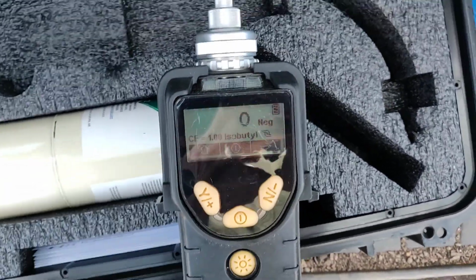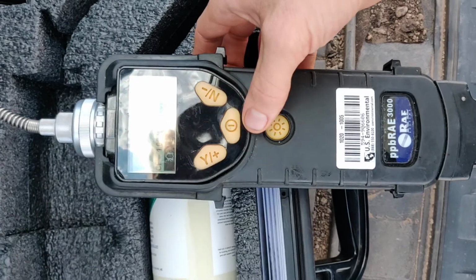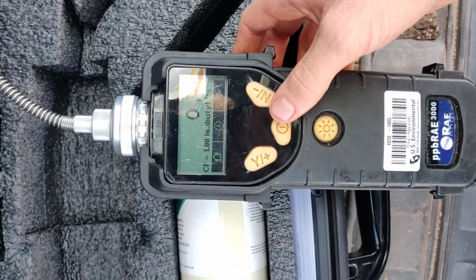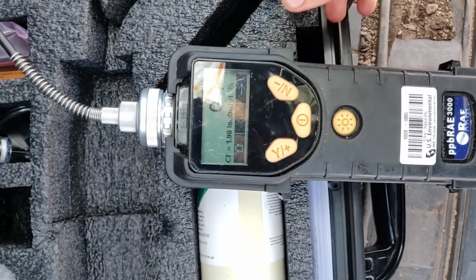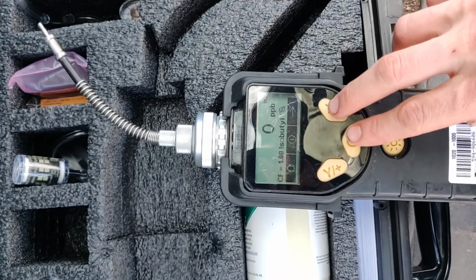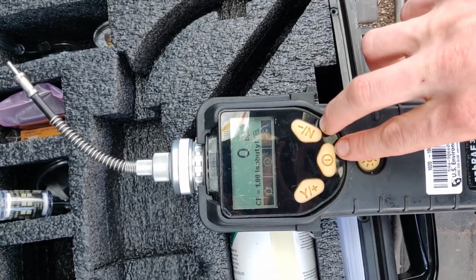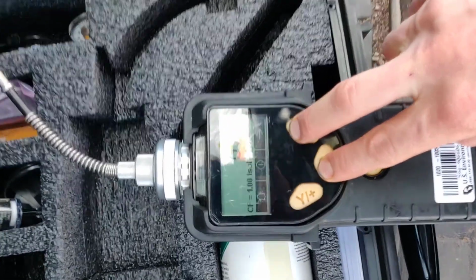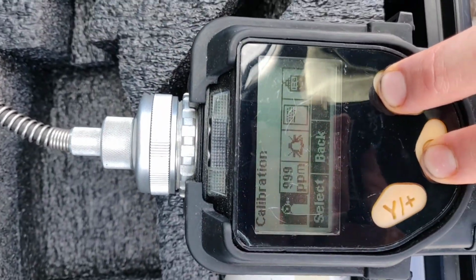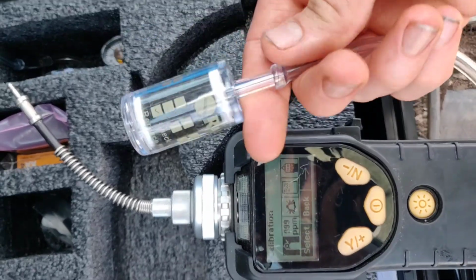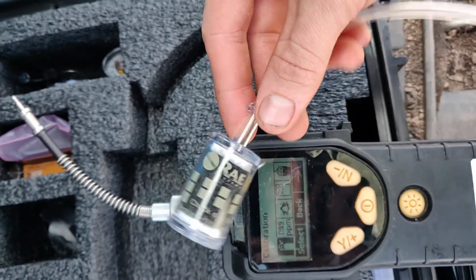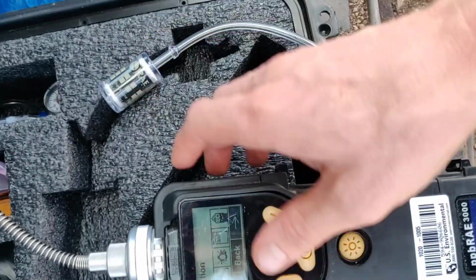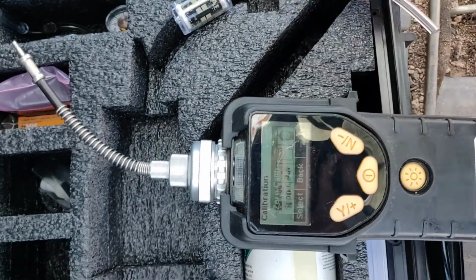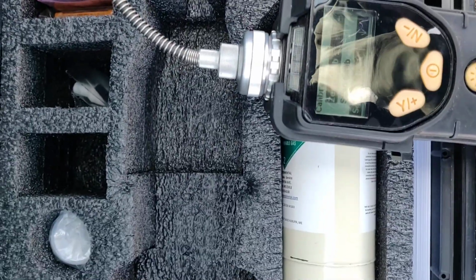Cut on. Show you the operation. You've got a lamp, a flashlight, good for going in the dark. Just a couple options to go through here. To do a field calibration, you hold these two buttons down. Calibration goes right to it. Then I'm going to take this. This is my zero filter. It is carbon, and carbon filters out all volatile components. They have large molecular structures.